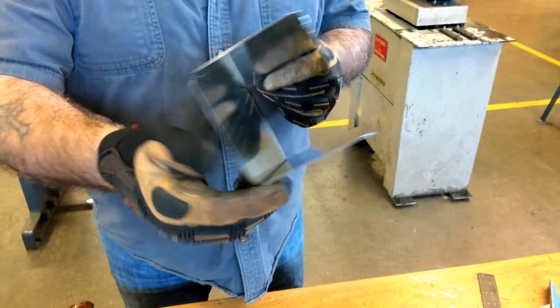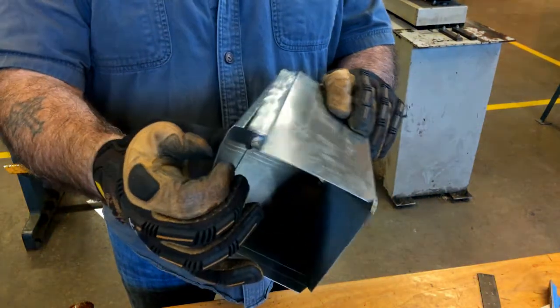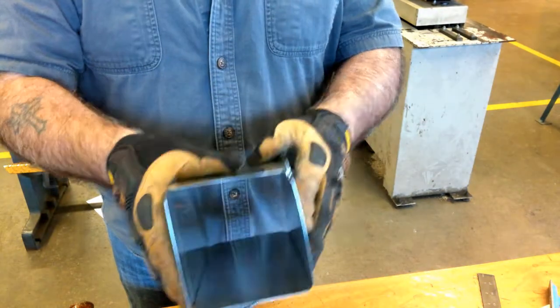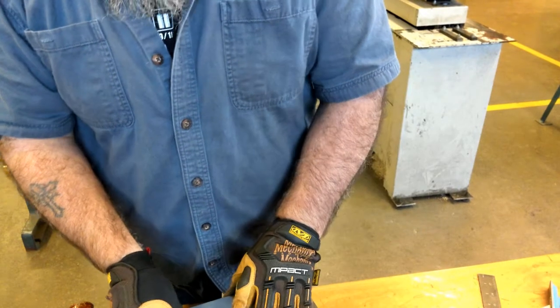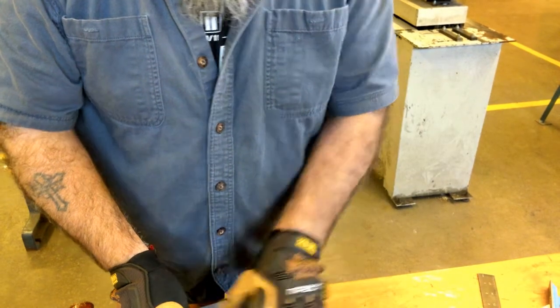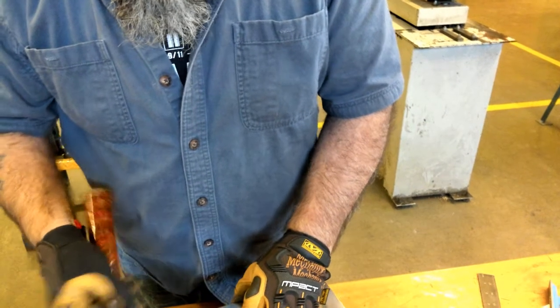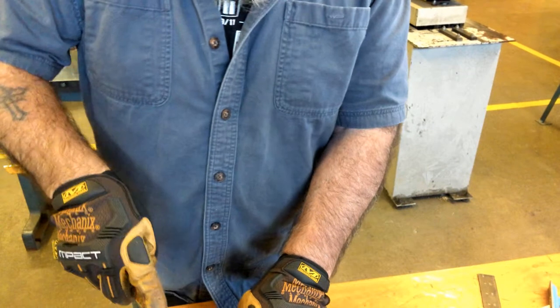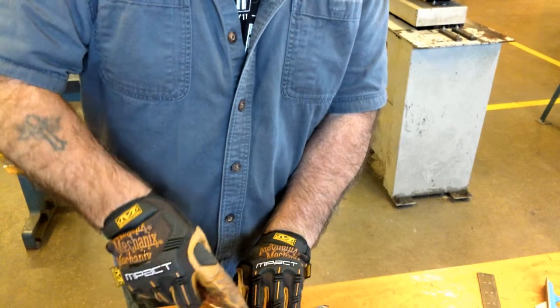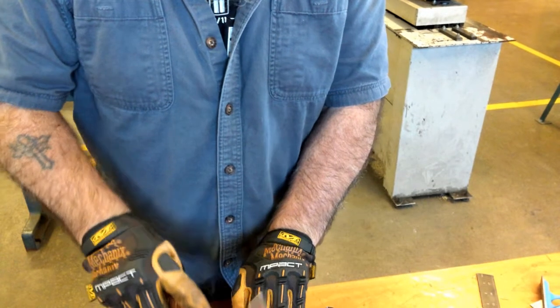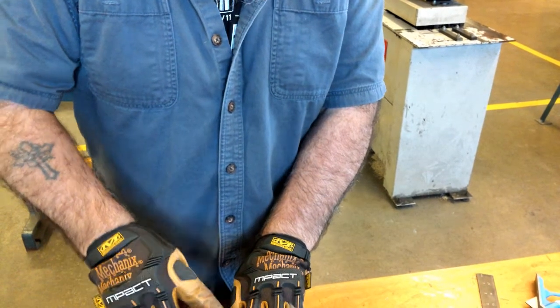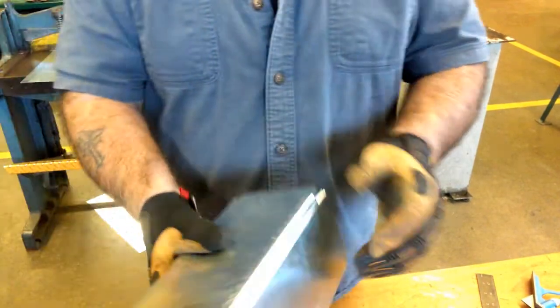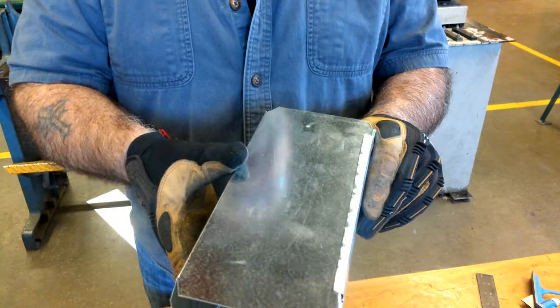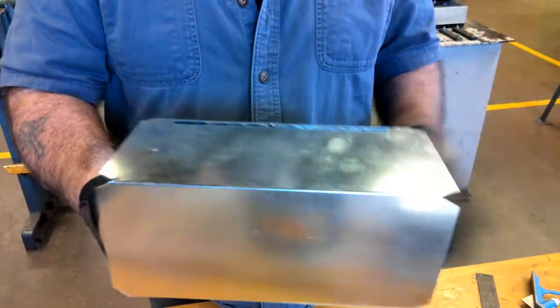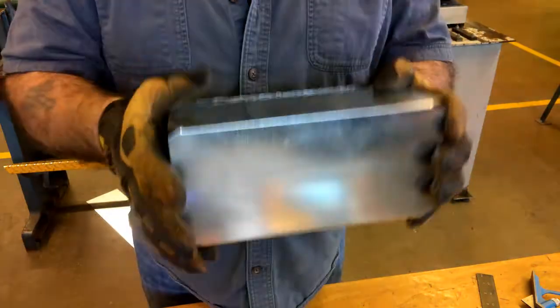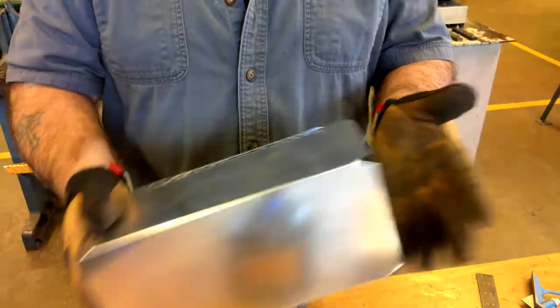Having formed my piece—again, it's one piece of metal that's going to become my ductwork—all I have to do now is insert my return flange into the Pittsburgh, make sure the ends of the ductwork line up, and simply hammer, or air hammer depending on the size of our ductwork, hammer it over. Again, depending on whether we're using TDC or slip and drive cleats, I would bend for slip and drive or whatever the case might be for our connections.